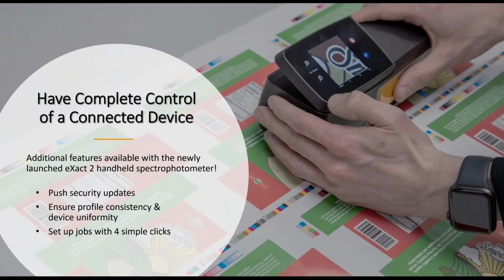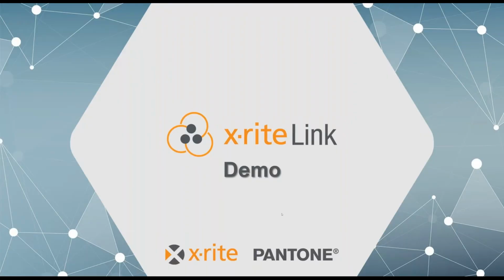And then finally, there's the connectivity within X-Rite Link. This is the newest device that X-Rite offers, and it has Wi-Fi capability and pairs well with X-Rite Link. So what it's able to do is allow you to connect between platform and device to do things like push security and firmware updates, ensure profile consistency with user profiles that can be sent to and from the instruments to help configure them, as well as jobs and other files that can really help to streamline a workflow and make you more efficient, so that you spend less time managing your spectrophotometers and more time running your organizations and your businesses. So with that, we will be able to pull up Link, and let's take a look at the platform itself.